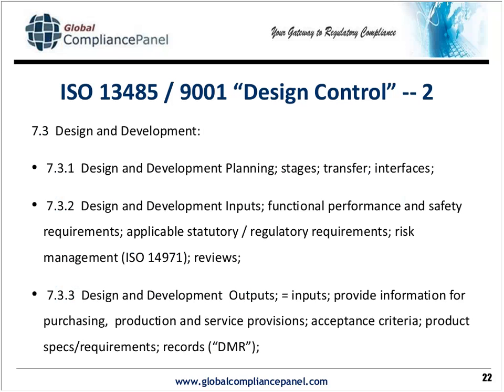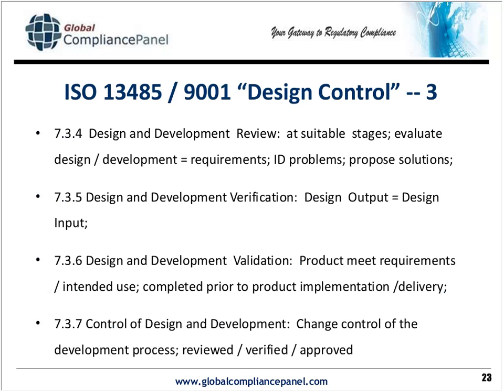You will notice a lot of the other elements of design control under ISO are very similar to 820.30 in terms of expectation for planning, for inputs, for outputs, determining that they match, for reviews, for verification, for validation, and for control.